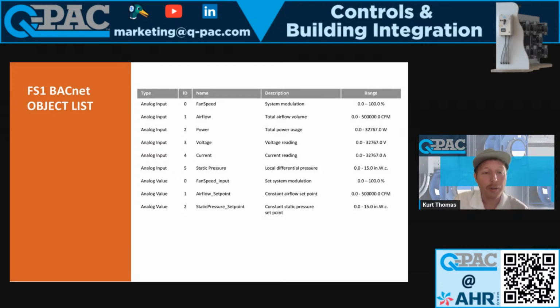Analog value 0, that'll tell you. So that's actually where you send the speed signal if you want to control the fans via BACnet without running an extra 0 to 10 volt wire. AV1, so that's your set point. If you want to change your set point via BACnet, if you're operating in constant airflow mode, and then constant static pressure mode. If you want to change, which you should, and they should be set once you figure out what you want them to be. But you do have the option to change the static pressure set point via BACnet.